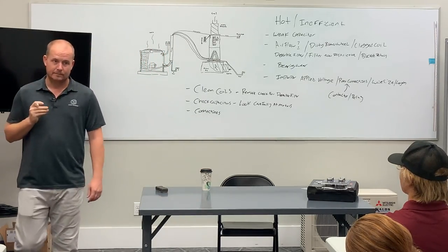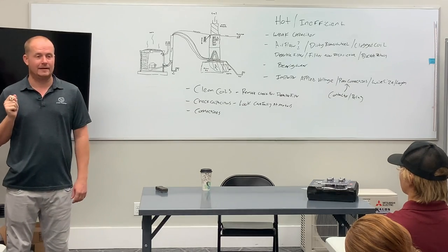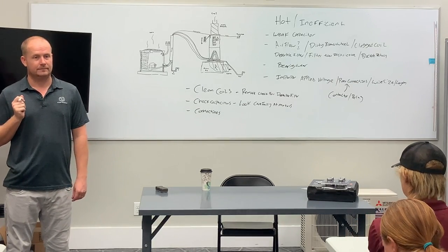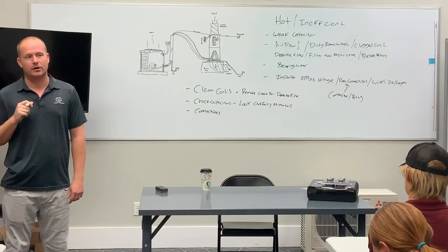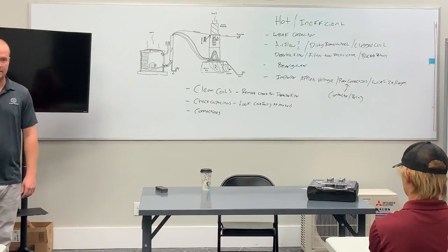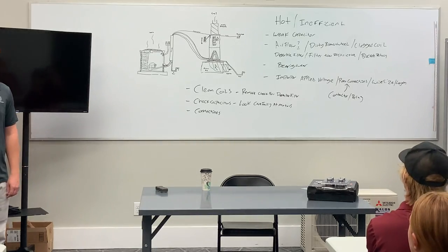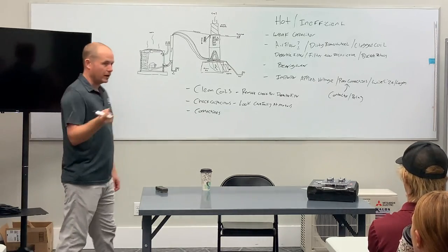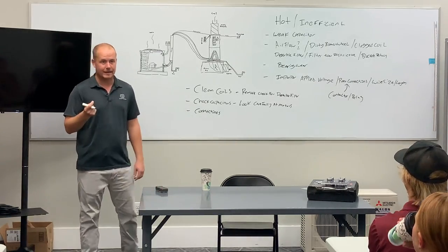Top of the capacitor. Top of the capacitor, and why? Why top of the capacitor? That's where people have been taking them on and off. A lot of times poor connections at a capacitor are user caused or technician caused, because you're pulling them on and off to test and you don't put them back on tight.